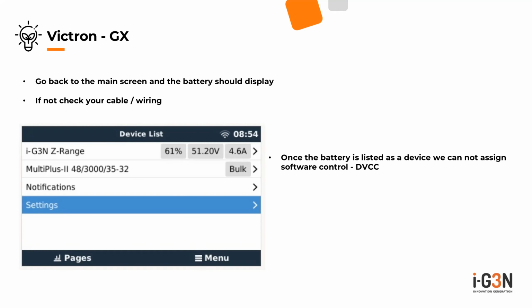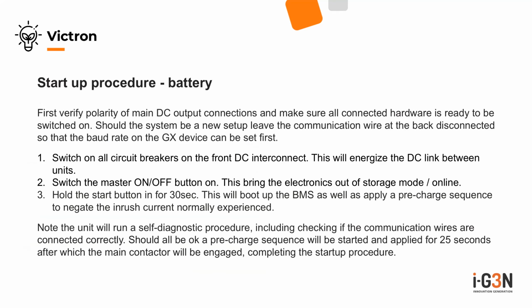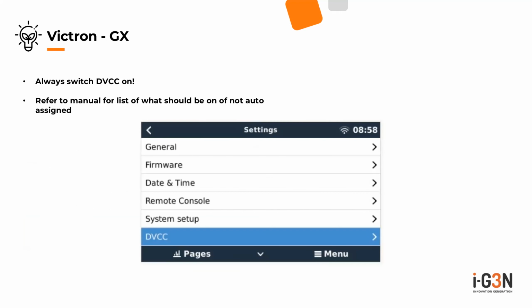When you start up the system, also verify your battery's polarity. As you switch on the system, it will do a self-diagnostic, then switch a pre-charge circuit on, enabling the system to power up. This normally takes about 20 to 30 seconds, then your system can boot up.